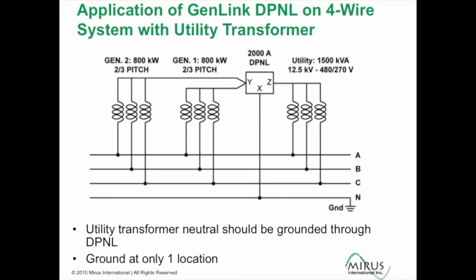This slide shows a configuration where we'd have generators, in this case similarly pitched generators, which are then paralleled with the utility transformer. So again, in this situation, the waveforms being created and supplied by the generators can have a slightly different wave shape than the voltage supplied by the utility. So we can get circulating currents. Here we show the neutral going from X connected to the neutral bus, and both the generator neutrals going through the DPNL, and the utility transformer neutral going through the DPNL. We're grounded in one location.